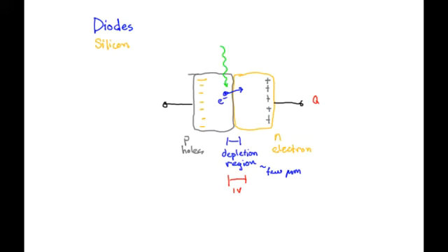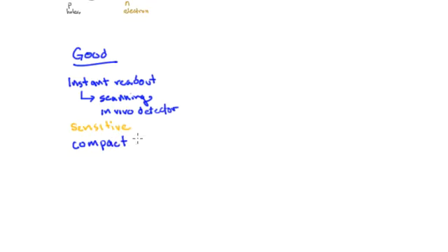There are some clear advantages and disadvantages to diodes. On the good side, they give an instant readout of the dose, so you can scan across a beam or do in vivo readings as a detector on a patient and get an instant readout on a surface. They're very sensitive—they can measure small doses accurately.